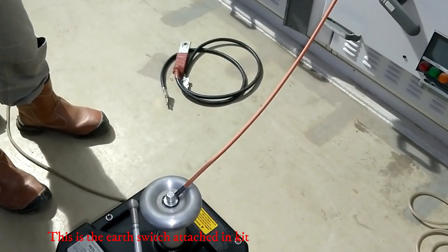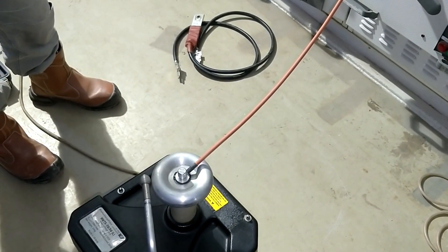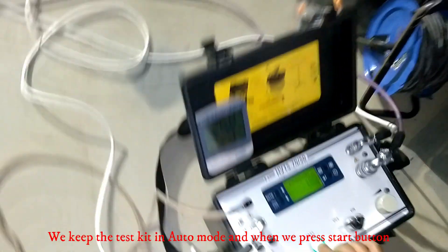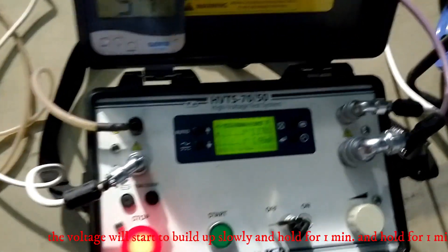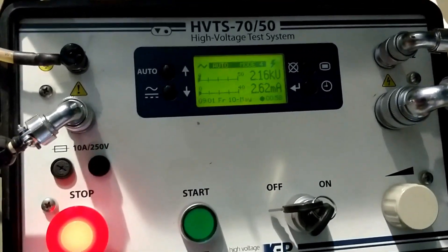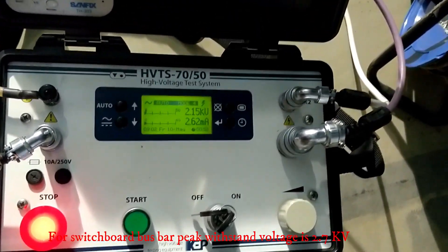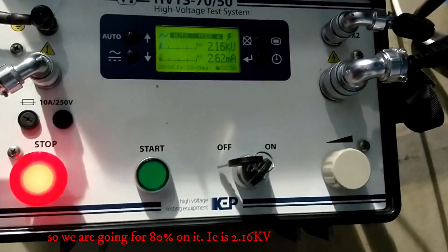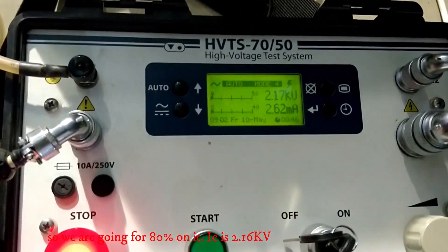This is the earth switch attached in the kit. We keep the test in auto mode and when we press the start button, the voltage will start to build up slowly and hold for one minute. In the switchboard bus bar, the peak withstand voltage is 2.7kV, so we are going for 80% of it — that is 2.16kV.